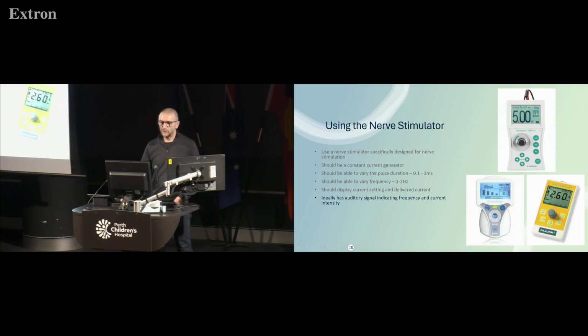And ideally, it should have an auditory signal so that you can hear the frequency of the stimulation and also the current intensity. So with the Pajunk and the StimPod, as the current reduces, the pitch of the tone starts to increase. So you can tell while your assistant is changing it that they're doing roughly what you've asked them to do.